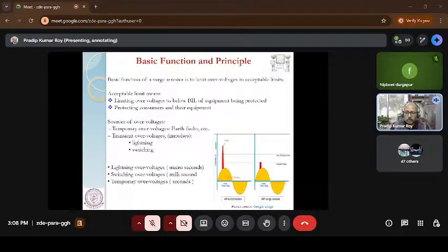Now, when I talk about overvoltage, overvoltage is mainly of two types. First is what people normally call temporary overvoltage, which is mainly because of an earth fault and survives a few seconds. Second is the transient overvoltage, which is done either by switching or by lightning. Switching mostly survives for a few milliseconds and lightning survives for some microseconds. Here we mainly talk about the transient overvoltage part, not the temporary overvoltage part.